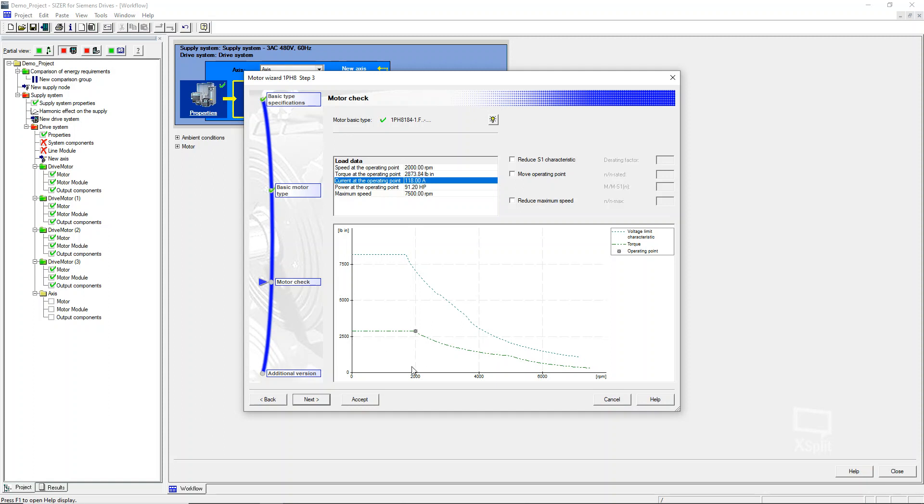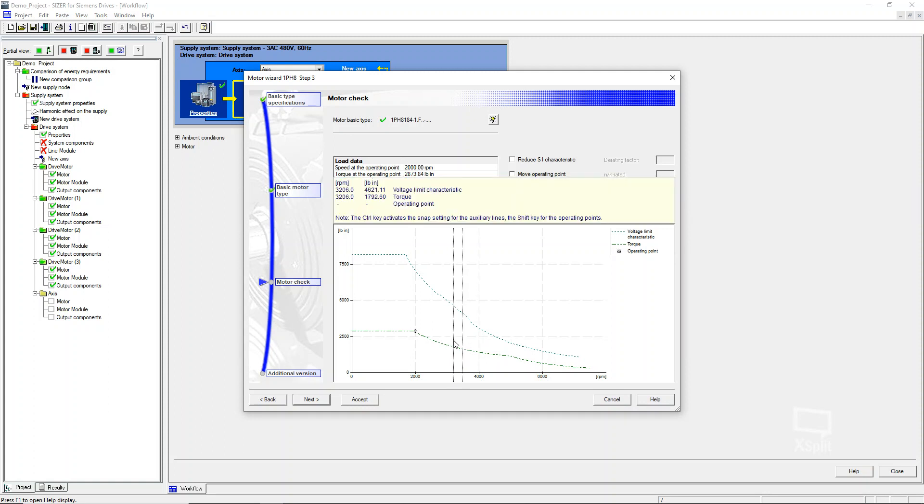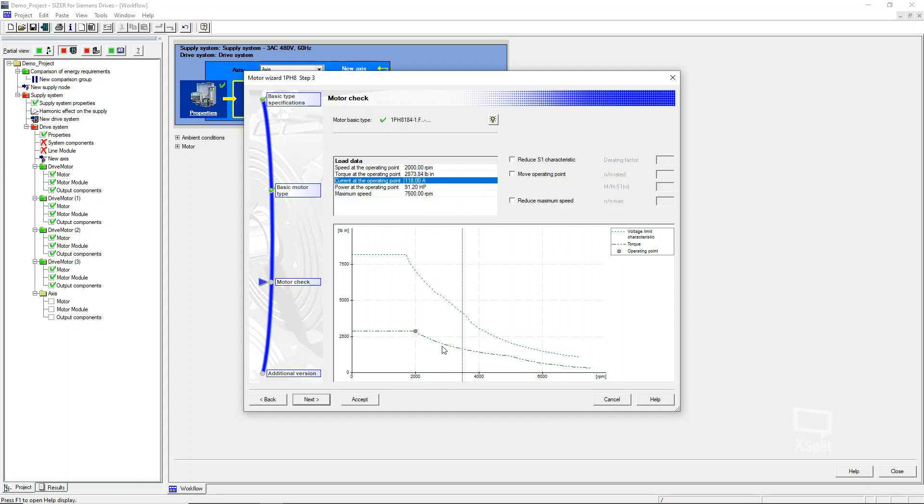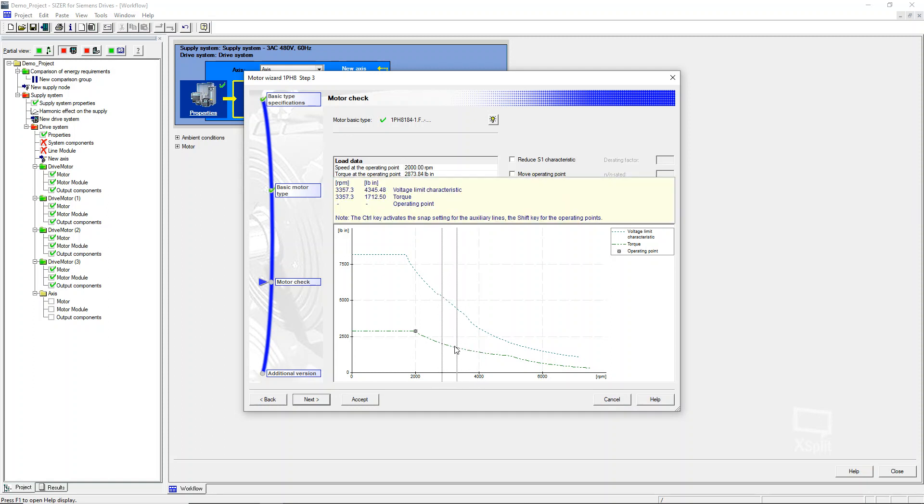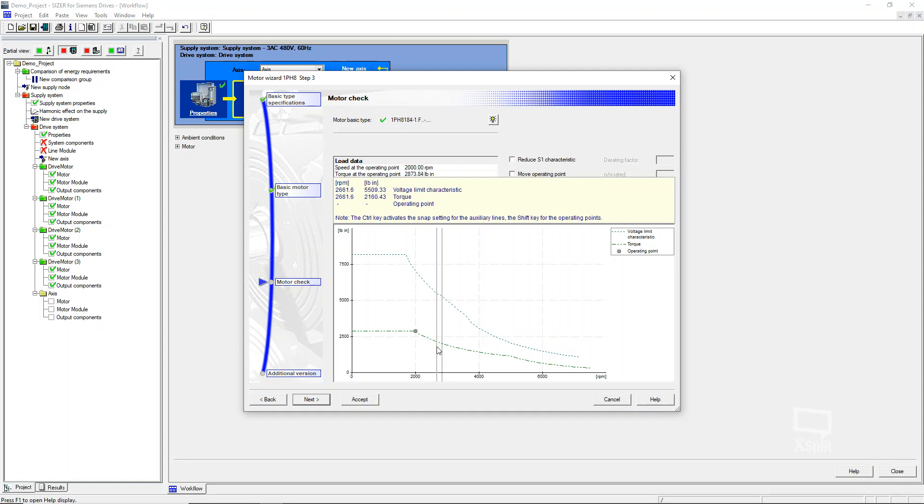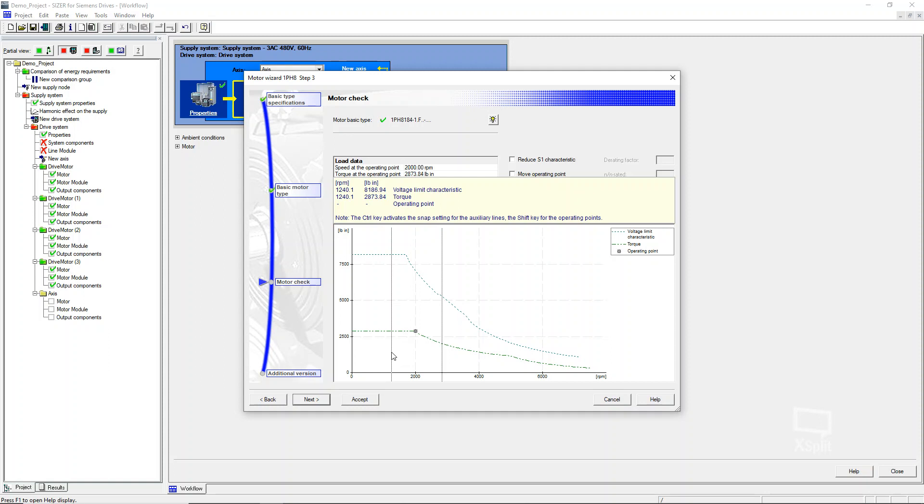So what we actually want to do is see what the available torque is out in this higher range, in what some people would call field weakening mode. So if we just double click, we will bring up a cursor and you can actually click and it will move that cursor now. And so what we're displaying here is a different RPM, what the available torque is. So remember, you have two curves, so you want to look at the torque curve. This customer is wanting something around 26 to 2700 RPM. And so you're looking at about 21, 2184 pound inches of torque available on this motor up there around that 2600 to 2700 RPM range.